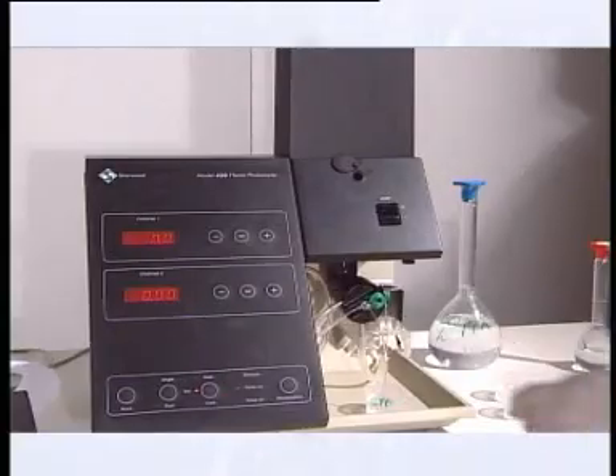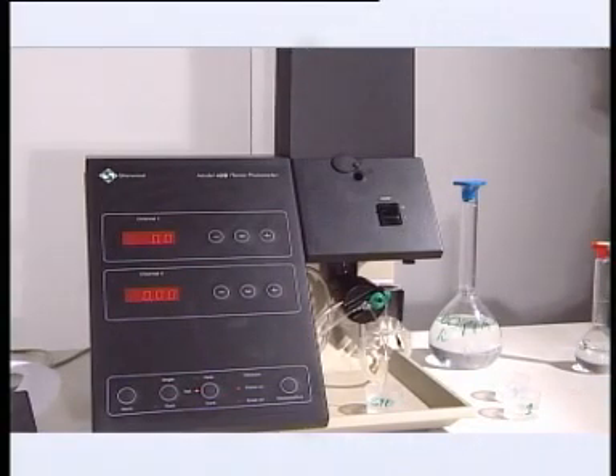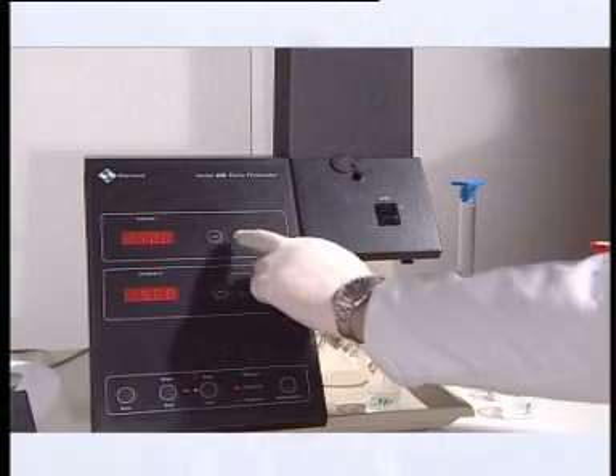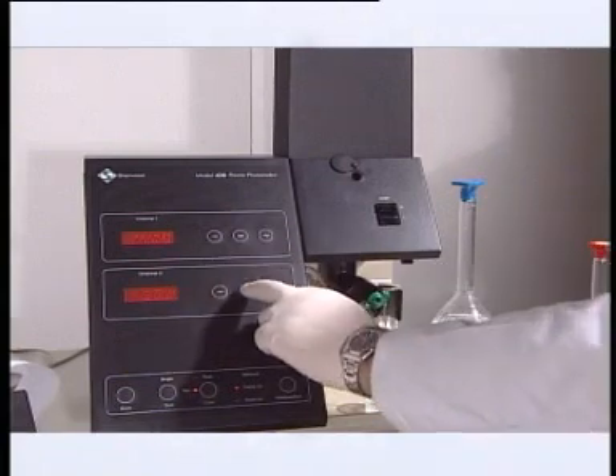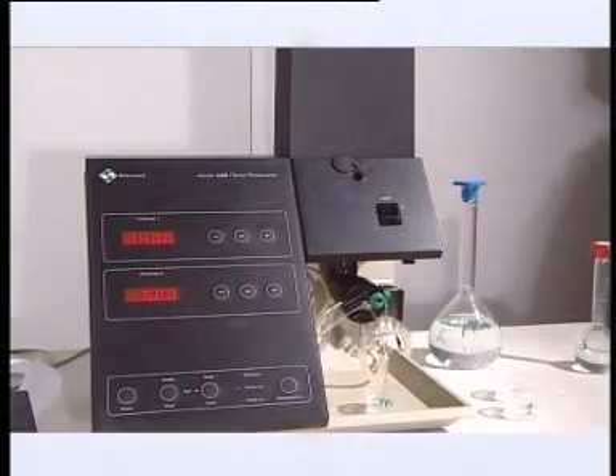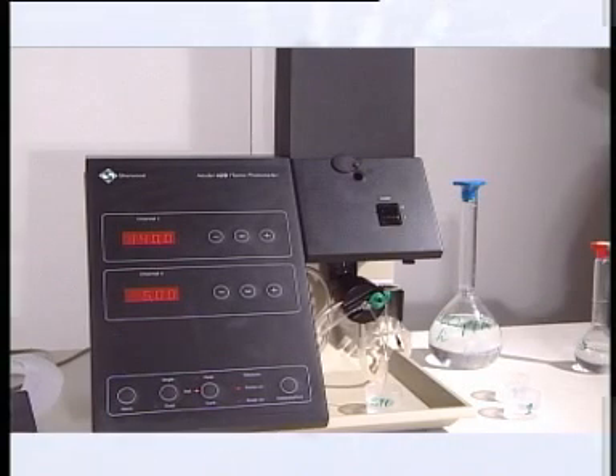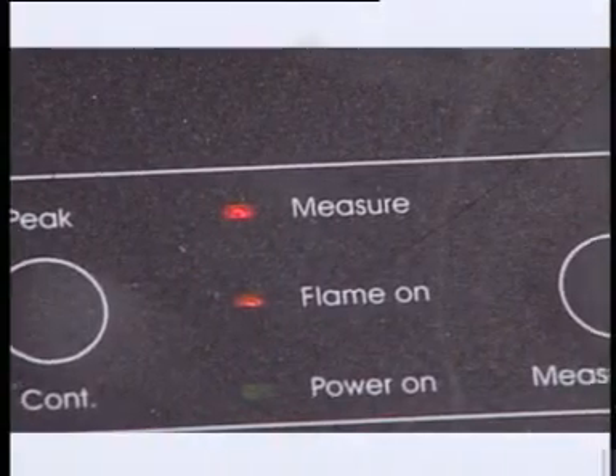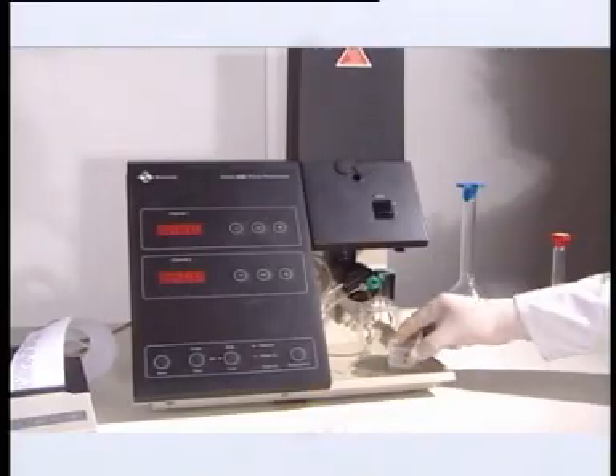Press Set on channel 1 and 2. After a few seconds, the display will change to the set value and cal will flash. Press Set again for each channel and the calibration will be printed. When the calibration values are set, the lithium internal standard value is set to 1.000. After 5 seconds, the measurement light will show and the unknown sample can be aspirated.